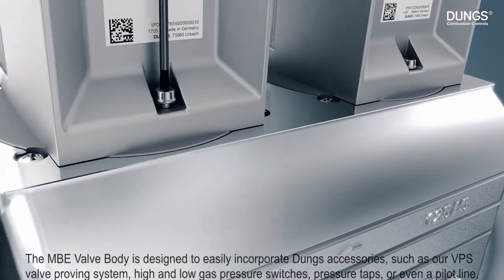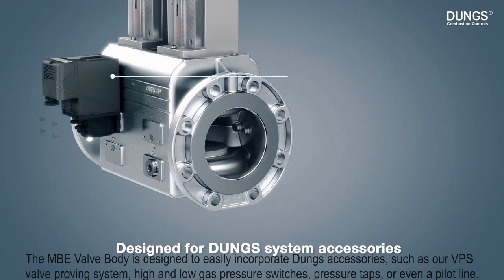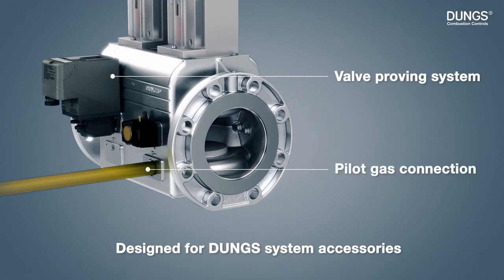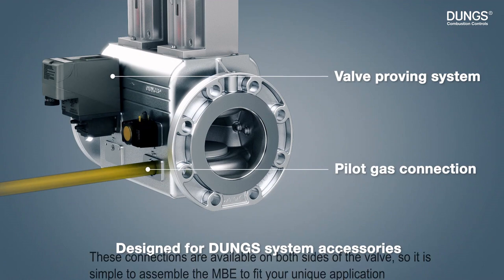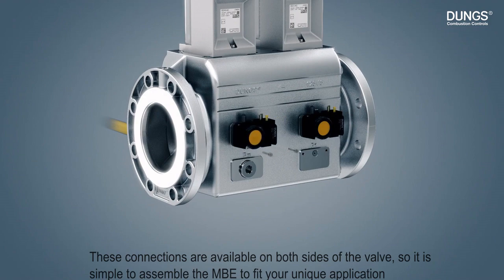The MBE valve body is designed to easily incorporate DUNGS accessories such as our VPS valve proving system, high and low gas pressure switches, pressure taps, or even a pilot line. These connections are available on both sides of the valve, so it is simple to assemble the MBE to fit your unique application.